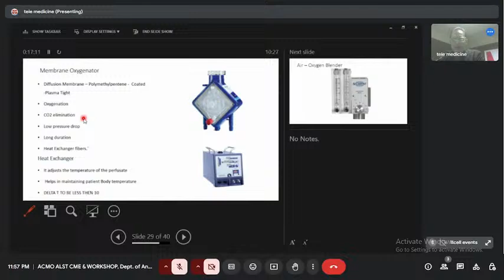Now, this is the oxygen blender. A similar way that you have with your ventilator machines or your anesthesia machines or your bypass machine. Okay, so if you have to increase the oxygenation, you go with the FiO2, and if you have to clear up the carbon dioxide, you have to go with the sweep gas flow. The sweep gas flow is how many liters per minute the air is running across your oxygenator. Likewise, you set your flow on your ventilator. When you are using Bains, you do it 10 to 11. When you are using your closed circuit, you do it 2. The same. Sweep gas is here. You start, the cardiac output is 5 liters per minute. On the opposite side, you start at 5 liters per minute, but you need to wash out more CO2. You can get as high as 10. Okay.